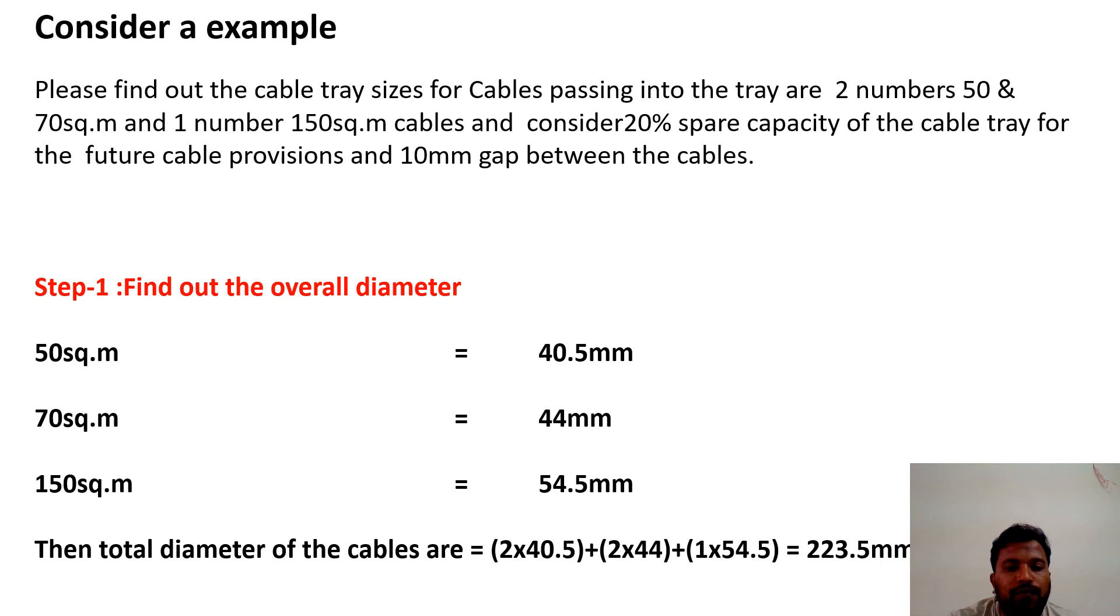Now we will calculate the total diameter of the cables. Add 2 into 40.5mm, I have 2 cables, so that's why I multiply by 2 into 40.5mm plus 2 into 44mm plus 1 into 54.5mm. If you are adding these values, you will get 223.5mm. This is the overall diameter of the cables.